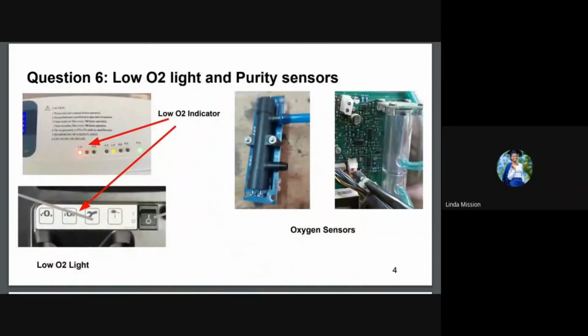Thank you, Maui. In most oxygen concentrators, the oxygen purity is monitored using an oxygen sensor connected to the control board that interprets the electrical signals from the sensor as either low or normal oxygen purity. So if the sensor is faulty or isn't well connected to the board, then weak signals or no signal will be sent to the control board. And this will lead to wrong interpretation of the oxygen purity in the system. And because of this, the LED for low purity will keep on illuminating despite having normal oxygen purity levels.